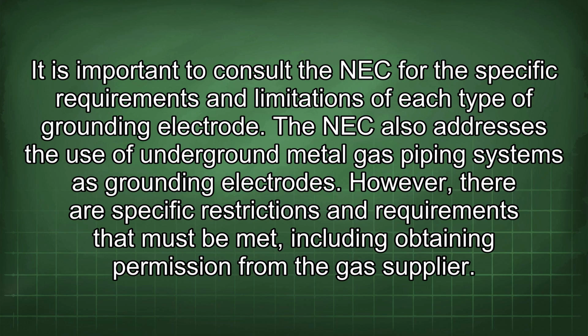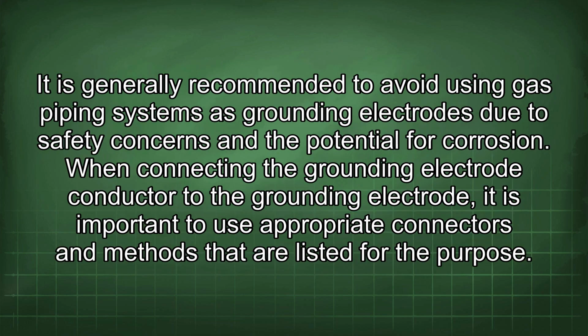The NEC also addresses the use of underground metal gas piping systems as grounding electrodes. However, there are specific restrictions and requirements that must be met, including obtaining permission from the gas supplier. It is generally recommended to avoid using gas piping systems as grounding electrodes due to safety concerns and the potential for corrosion. When connecting the grounding electrode conductor to the grounding electrode, it is important to use appropriate connectors and methods that are listed for the purpose.